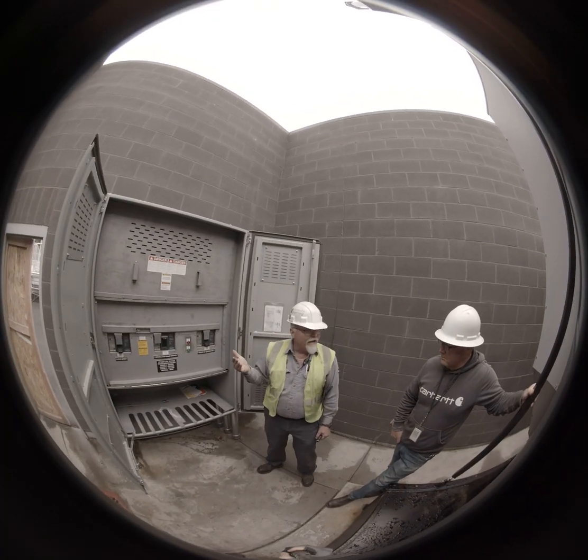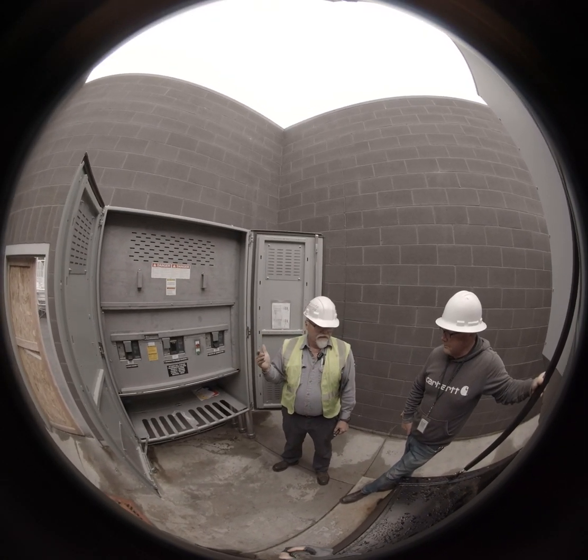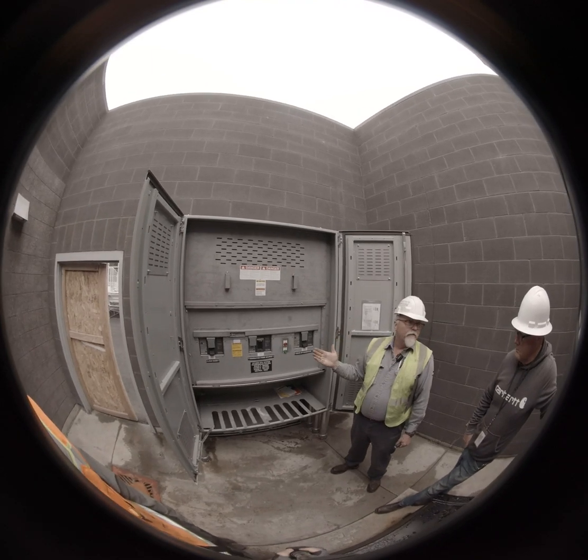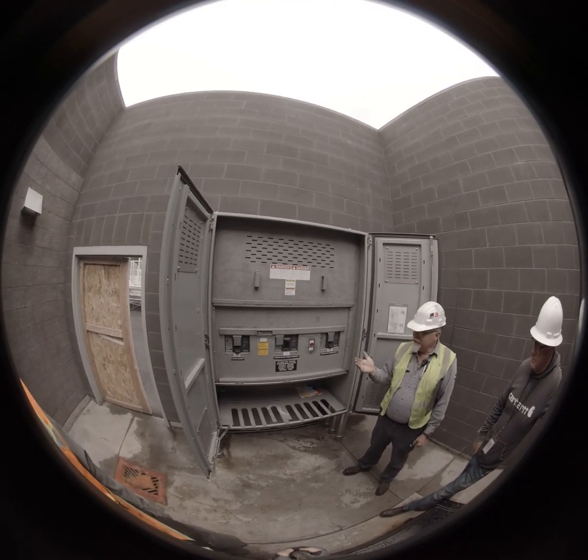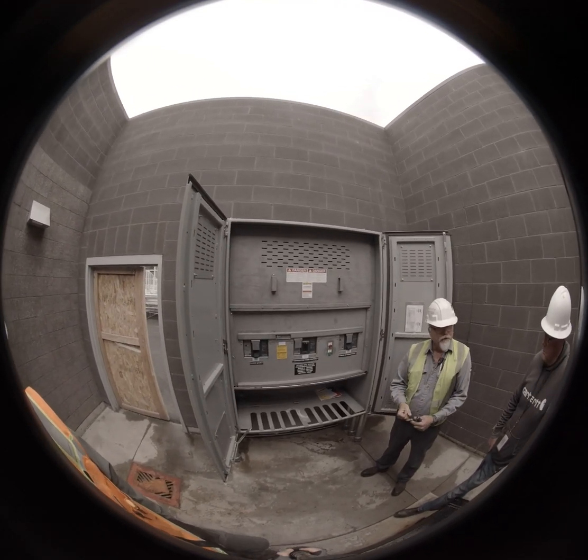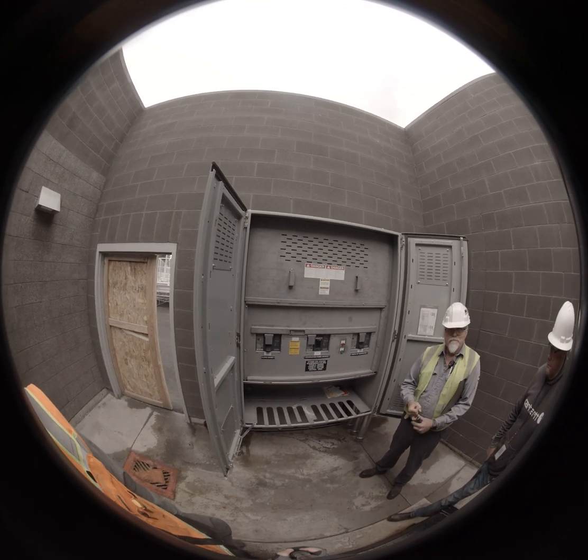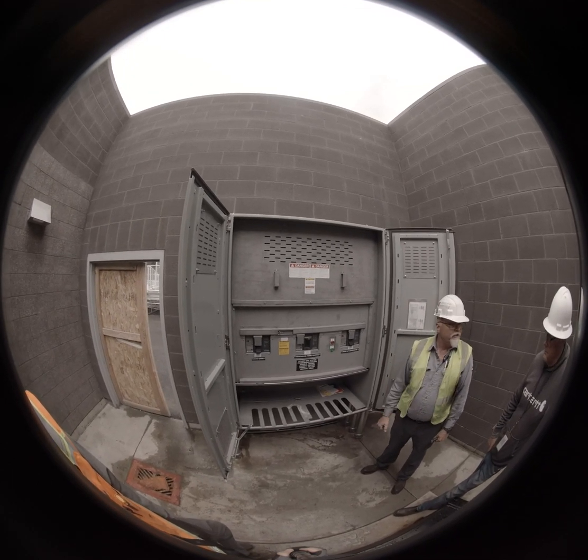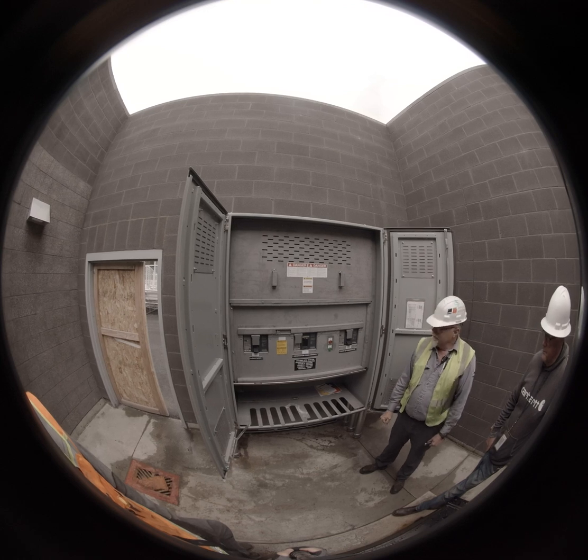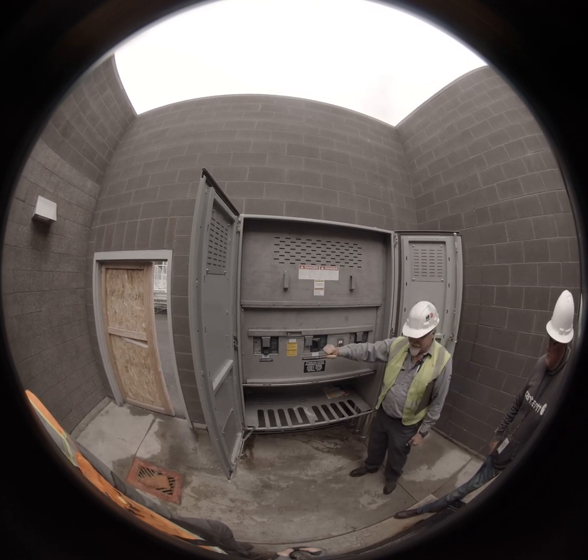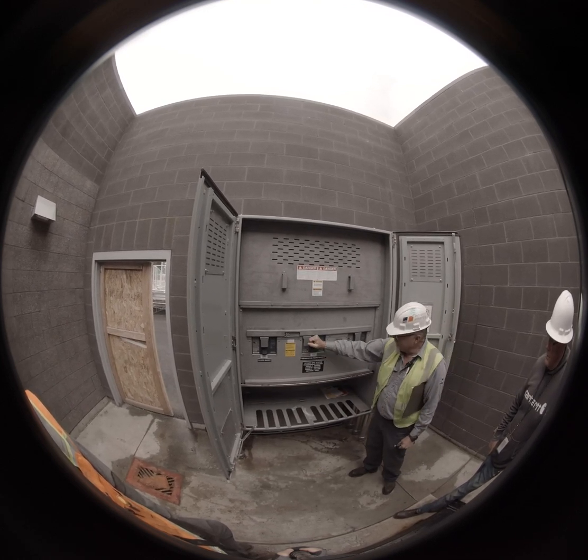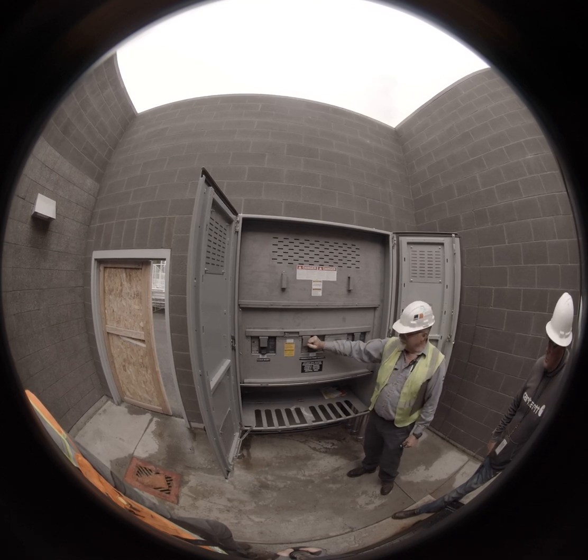Is the FoxFab tap box. They make a lot of different variations of these. This particular one is set up so that you can not only load bank, but also back this up with a temporary generator set. The main breaker for the generator set, the permanent generator set, is right here in the middle. It should always be left on.